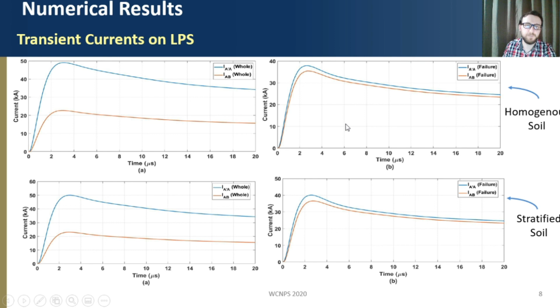So we can see here that in the whole condition we have these currents, but as we have the failure, the damage condition, the current AB increases significantly. This is for the homogeneous soil. When we have the stratified soil, we can see they present lower peaks in comparison with the first case, but they present similar behavior in the damage condition. They are almost the same currents. This is explained because in the stratified soil the soil resistivity is lower than in the first case, so it is expected to have lower currents.